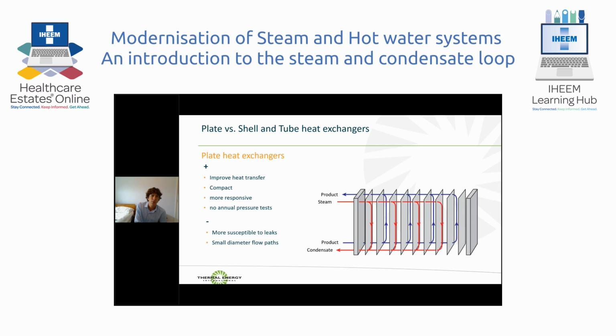Plate heat exchangers have a very high surface area, which makes them compact and gives them high heat transfer rates. They also have very low volumes, which means that they're responsive to changes in demand, and also therefore don't require any annual pressure tests. They can, however, be susceptible to leaks due to the number of seals between all the plates, and also to blockages if you've got debris or scaling within the steam or hot water due to the small diameter flow paths. On heat recovery systems, the economic approach temperature is much lower, which can significantly increase the potential for heat recovery compared to a shell and tube heat exchanger.